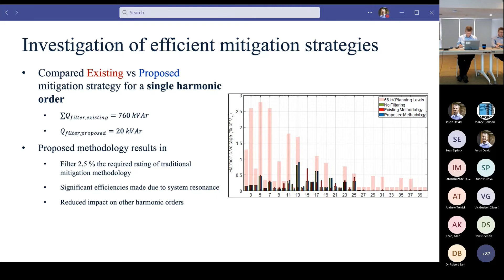But what I suppose the highlight here is this relation: using the proposed methodology, the size of the filtering can actually be shown to be a fraction of the required filter if the filter is connected away from the point of resonance on the network. And that is not an estimate, that's not a rough guide, that's an exact value. It mathematically works out that way: to achieve the same impact, filtering external to the point at which the impedance is the highest, you require a much larger filter, ultimately, is what that's saying.